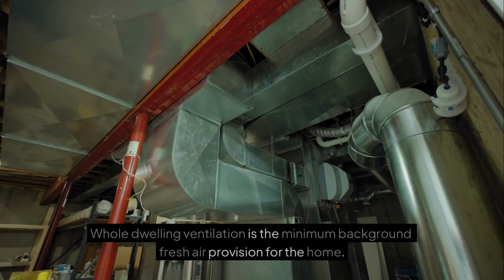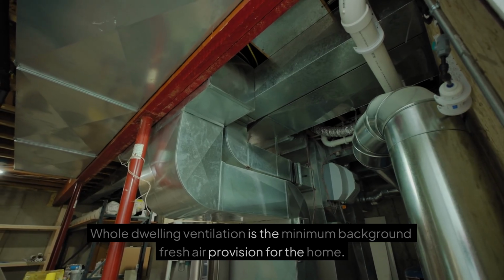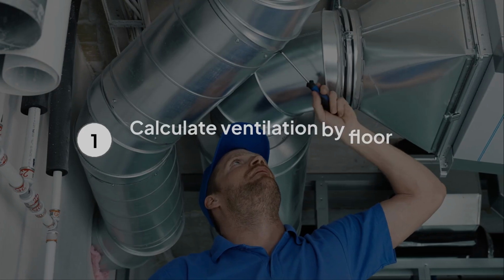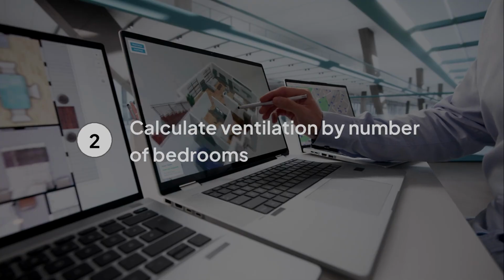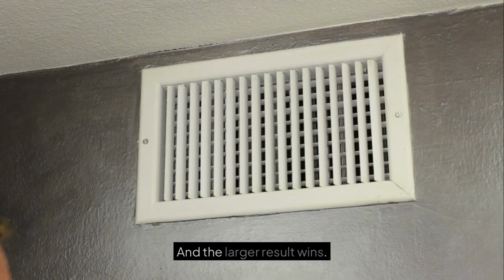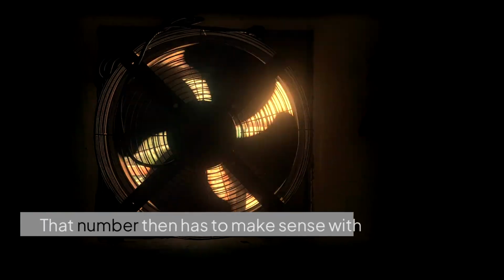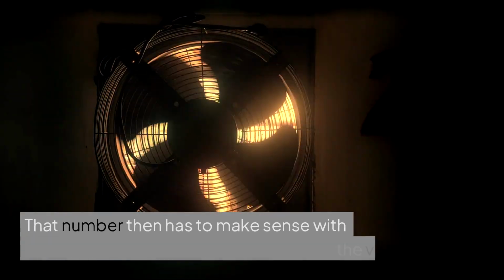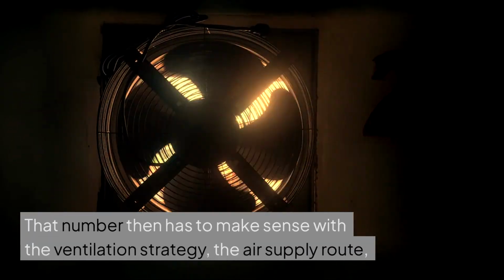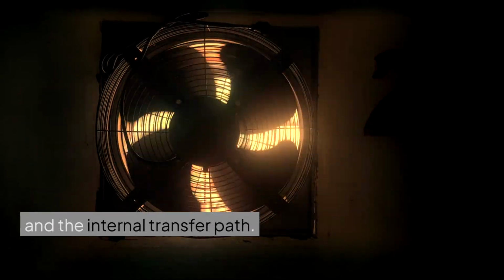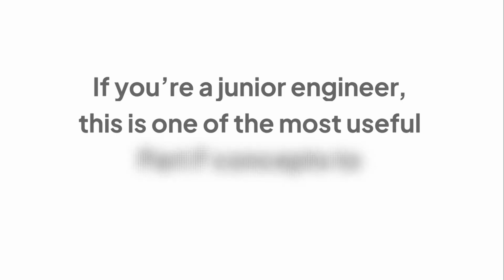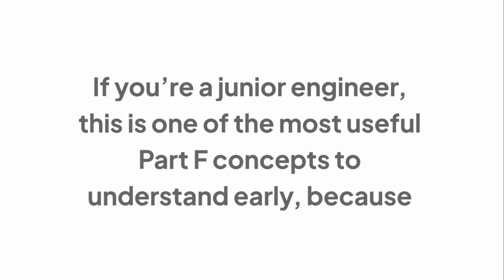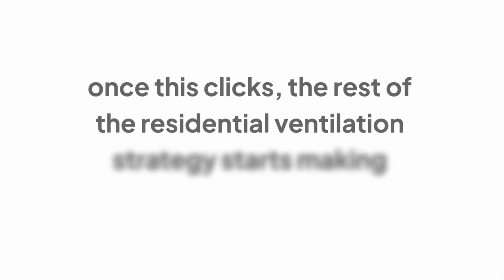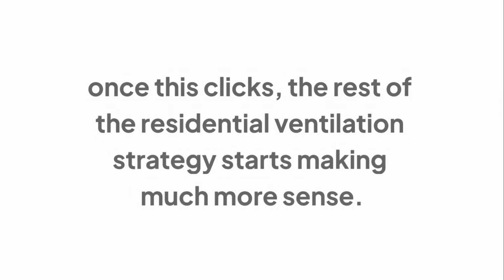Whole dwelling ventilation is the minimum background fresh air provision for the home. You calculate it in two ways, by floor area, by number of bedrooms, and the larger result wins. That number then has to make sense with the ventilation strategy, the air supply route, and the internal transfer path. If you're a junior engineer, this is one of the most useful Part F concepts to understand early, because once this clicks, the rest of the residential ventilation strategy starts making much more sense.